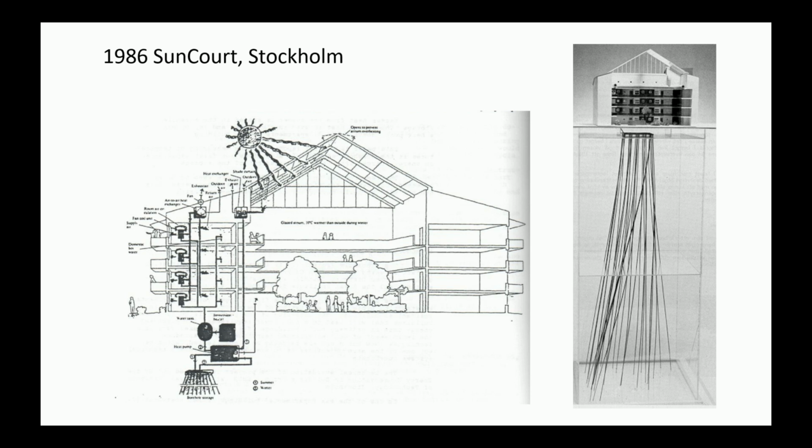project in Stockholm where, as you can see to the left, there are 2 buildings enclosing an inner court with a glazed roof. During the summer, it gets very warm if they don't remove the heat, so they remove the heat and put it into the borehole. So there was a storage. It was not an elevated temperature, but due to the heat balance, it's a fairly balanced system, so they could put the boreholes fairly close. And you can see to the right what it looked like.